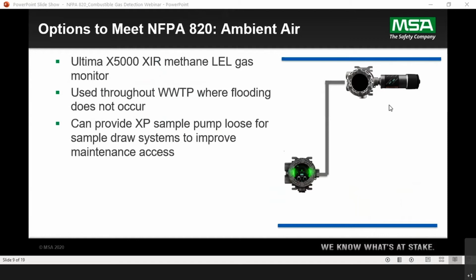And one thing about ambient air, you want to make sure that you can't have flooding. So typically for methane, it's high, you don't have the flooding, but we can provide sample draws, which I'll talk about. Sometimes sample draw is good if the ceiling's very, very high and the users don't want to go up, and the access is really bad, like in a digester building. Then we'll put a pump right next to the transmitter, and we'll pull a sample from the top of the ceiling to the detector itself.